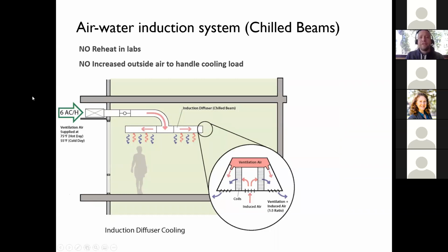So what we have for chilled beams is we actually take that ventilation air that the DOAS system is delivering to the space, and we push it through this little box. The blow-up here in the middle is an illustration of what that box looks like. In the red area, the air is blown into that red portion and pressurized, and then it's shot through nozzles at pretty high velocity out into the room.